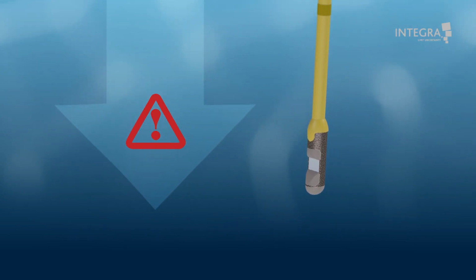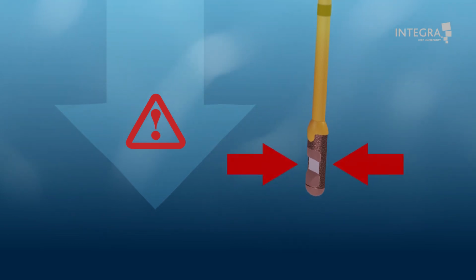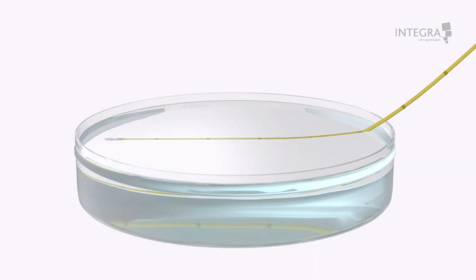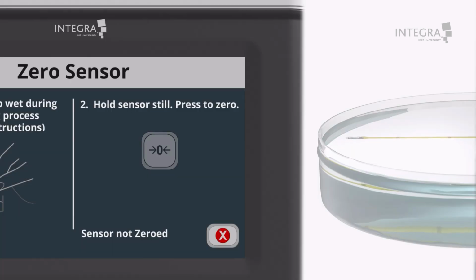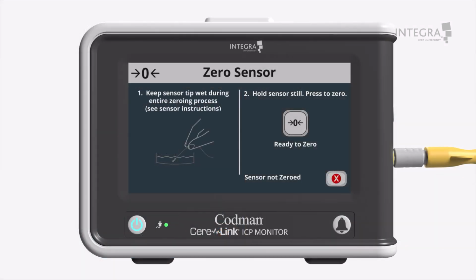Do not submerge the tip of the ICP sensor vertically in a deep pool of sterile water or sterile saline. Doing this will impose a hydrostatic pressure on the ICP sensor diaphragm that is higher than atmospheric pressure, resulting in an inaccurate 0 reference. Hold the sensor still without applying any external pressure to the tip apart from the sterile saline. If the device senses the sensor is moving, a 0 button will not be available. Press the Ready to Zero tab. You will note a 0 in progress on the screen. When sensor zeroing has been successful, the date and time will be displayed on the screen.